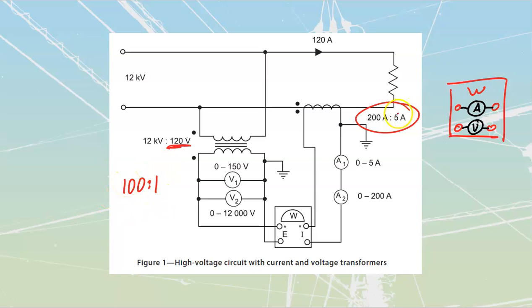Same with this one over here. If I take my 200 to 5, you could just do 200 to 5 in your head. That will give you a 40 to 1 ratio. What we will be able to do then is take that ratio, and because my watt meter is combining both of them, my watt meter is going to have a watt meter multiplier that comes off of that.